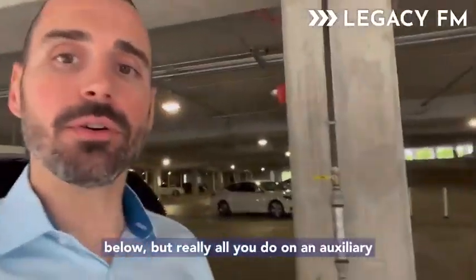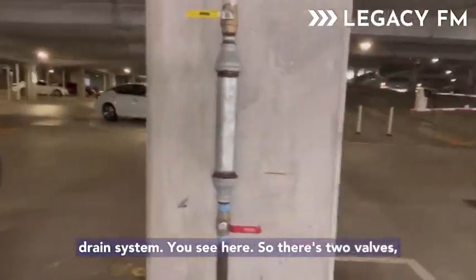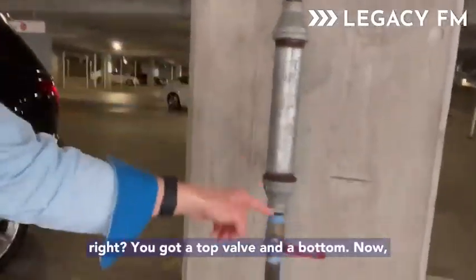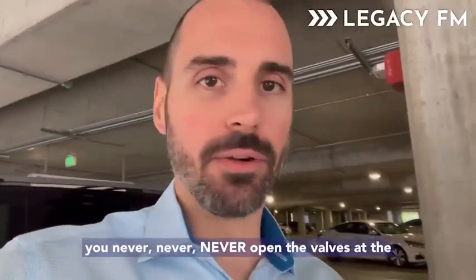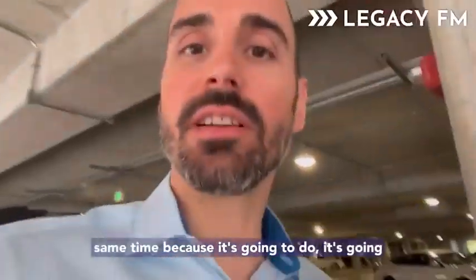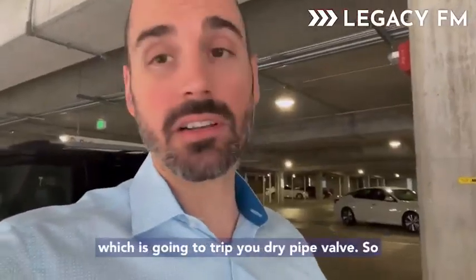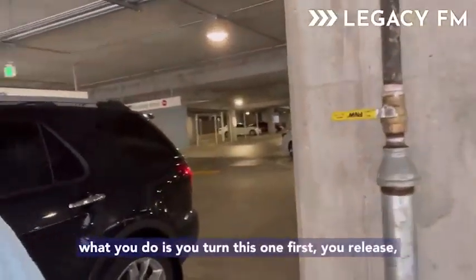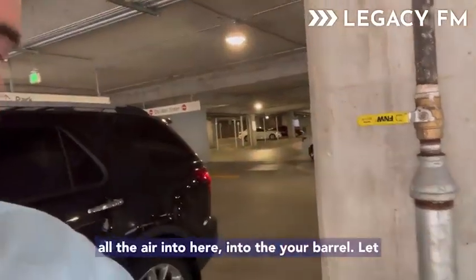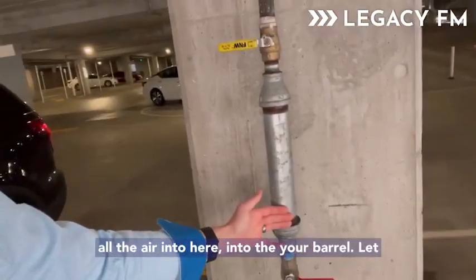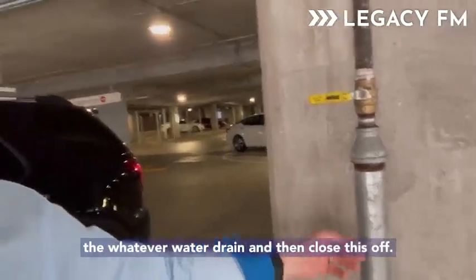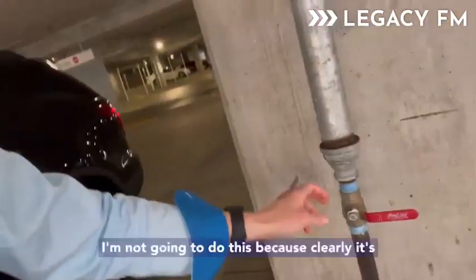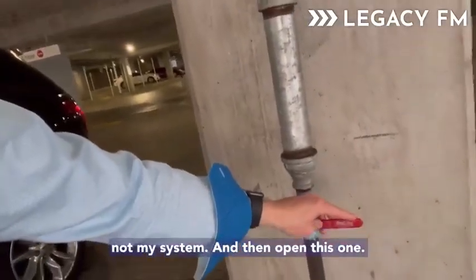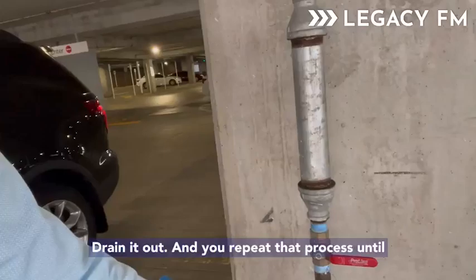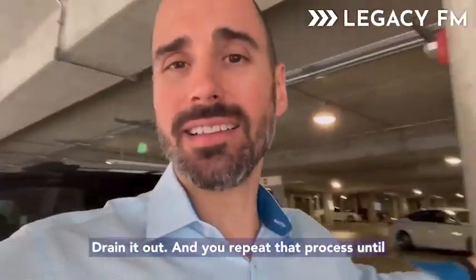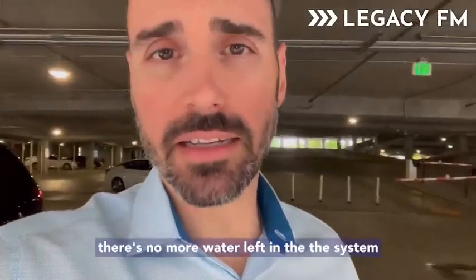But really, all you do on an auxiliary drain system, you see here, there's two valves, right? You've got a top valve and a bottom valve. You never open the valves at the same time, because what's it going to do? It's going to release all of the air from the system, which is going to trip your dry pipe valve. So what you do is you turn this one first, you release all the air into your barrel, let the water out, and then close this off. I'm not going to do this because clearly it's not my system. And then open this one, right? Drain it out, and you repeat that process until there's no more water left in the system.